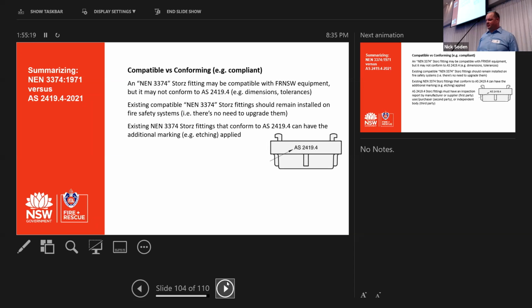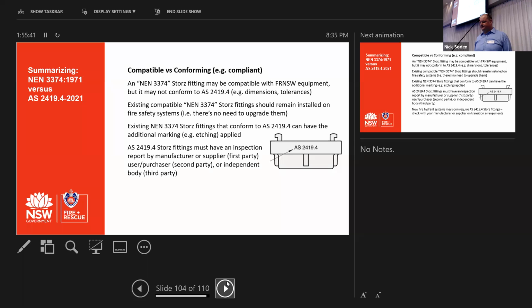Existing NEN 3374 Storz that do conform to Part 4, such as some of those manufacturers I mentioned, can actually just have the additional marking applied. So if you use a seller and they're supplying a certain product and it conforms, all they need to do is photo etch Part 4 on the side of the rim. And AS 2419 Part 4 Storz fittings must have an inspection report by the manufacturer or supplier if it's first party, by the user or purchaser if it's second party, or by an independent body if it's third party. So as long as you get that comprehensive inspection report, that's fine.